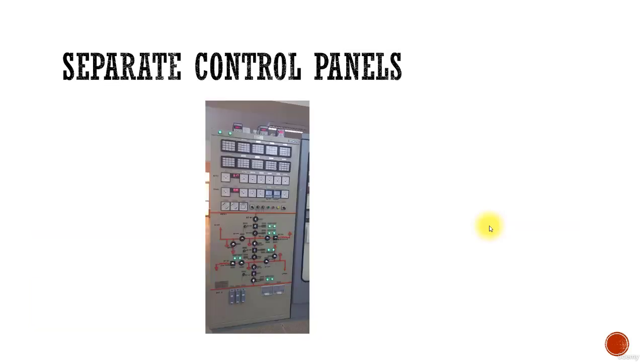Also, if you are going for AIS and GIS, apart from the protection panels and separate switchgear, you need a separate control panel as well in the control room. So here you can see all the indications are there, alarms are there, you can see the synchroscope is also there. So you need to have all this equipment. So by installing MV switchgear, we are optimizing the cost, and we are optimizing the space or footprint requirement. So that's why you will see the MV switchgears. You can see these switchgears, which are a combination of all these things, and these are installed mostly at the medium voltage level.